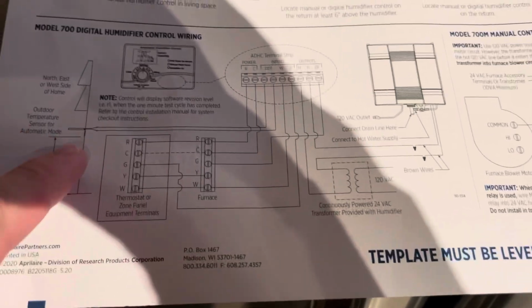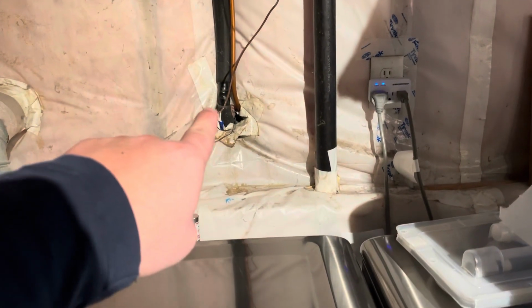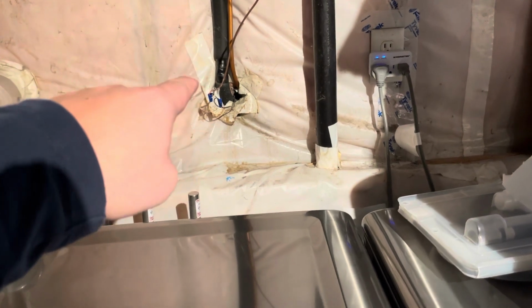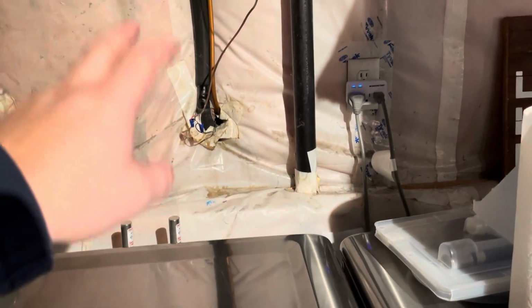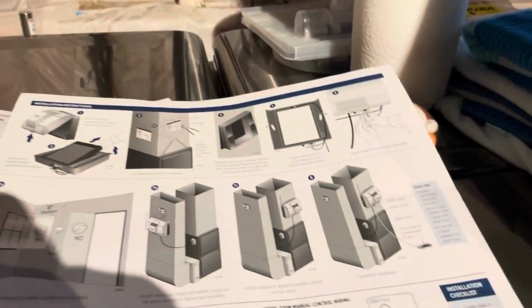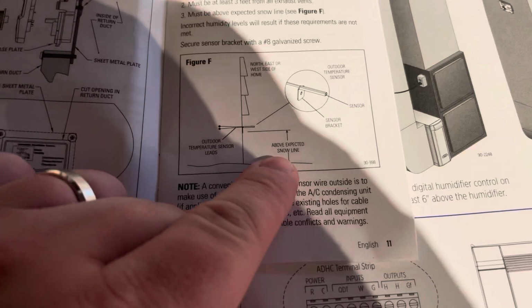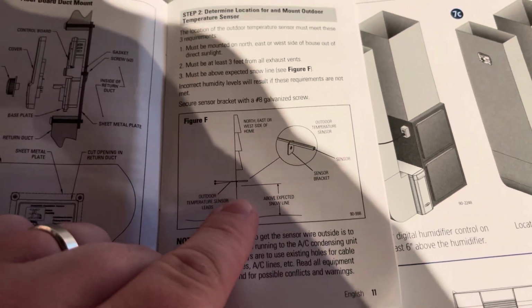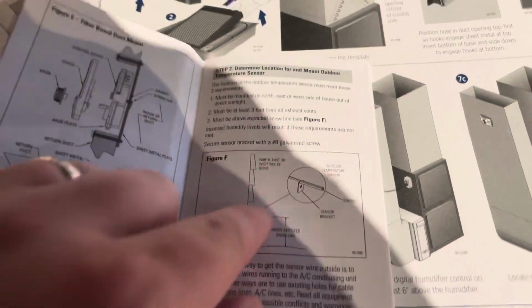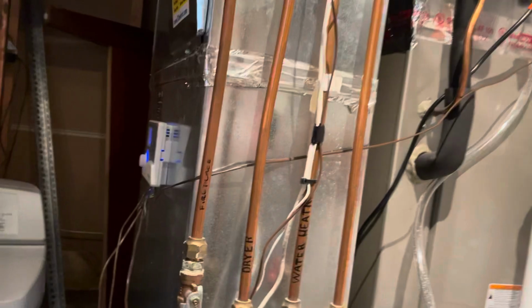The outdoor temperature sensor, I ran mine through copper line and cable work that's going out to the AC condenser outside, and I followed the recommendations in the manual for that, where they wanted it to be above the expected snow line. I'm in Minnesota, so we get some snow, and they wanted it to be 3 feet away from any exhaust vents. My dryer comes out the wall there, so I just made sure I was 3 feet away from that on the wall. I fed that up and over and down and into the controller. So that was fairly straightforward.